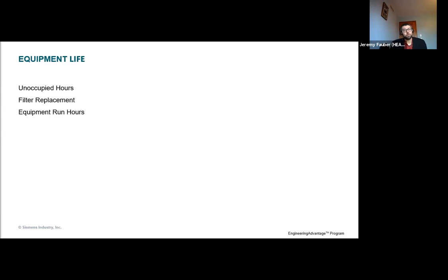The other item is equipment run hours. If you are doing unoccupied hours operation, then your equipment run hours are going to increase somewhat proportionally to those unoccupied run hours. So in the example I gave before of going from 13 hours a day to 16 hours a day, Monday through Friday, that's about a 25% increase. You're probably going to get about a 25% increase in equipment run hours in a year. Probably slightly less, because a few of those hours would have been some unoccupied operation at some points, but more or less the same increase.